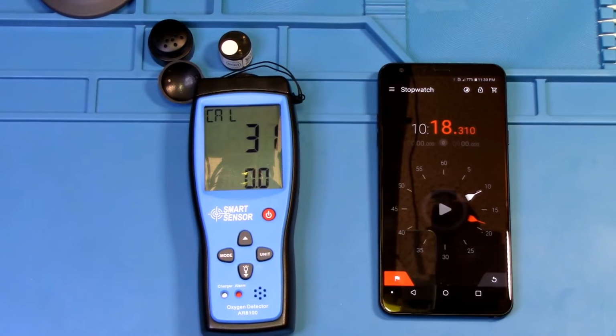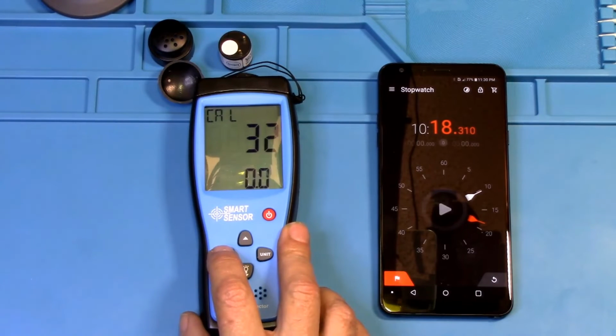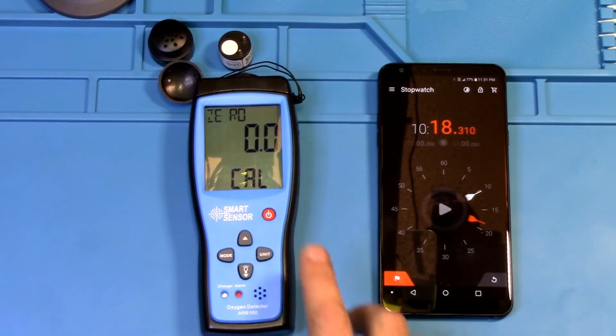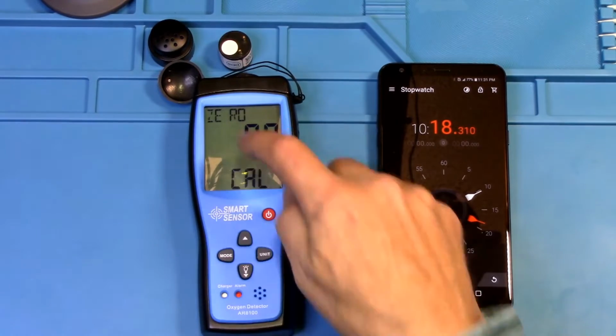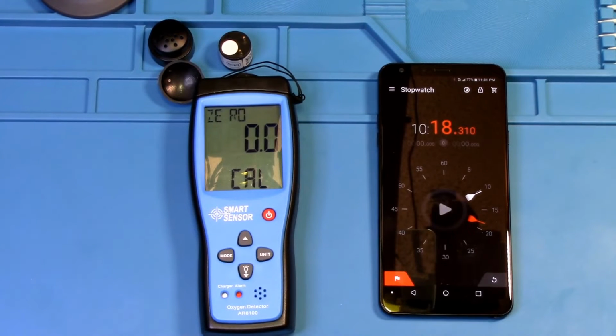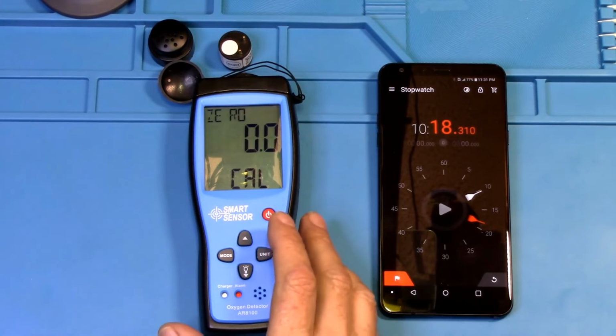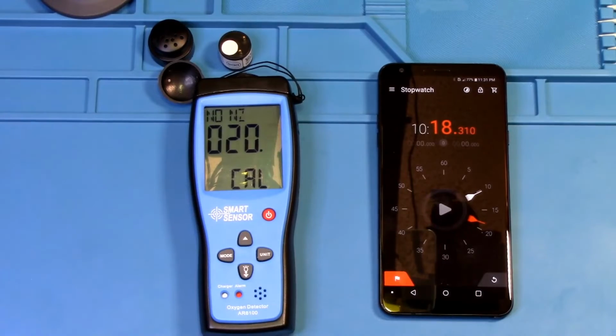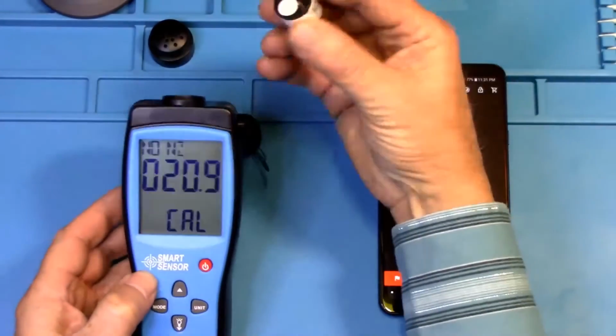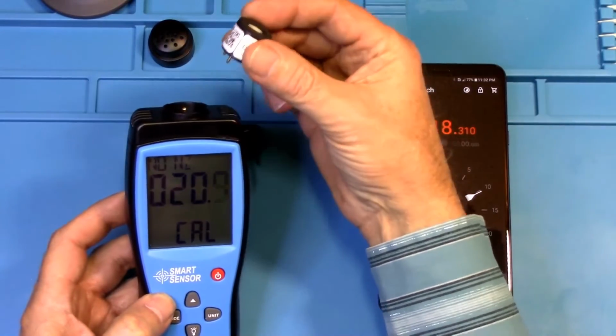Okay, it seems to have stabilized around 31, 32. But yeah, it doesn't really matter what the numbers are as long as it gets down to where it's stable within a couple numbers or so. The next step we're going to do is press the mode button again, and it will show 0.0 with cal at the bottom, and it says 0 at the top. Okay, now we will press the mode button again to display the oxygen value. Okay, when the reading is 20.9, that's when you want to reinstall the oxygen sensor.